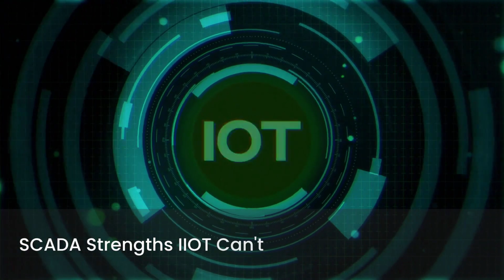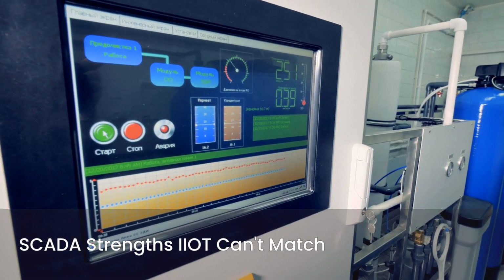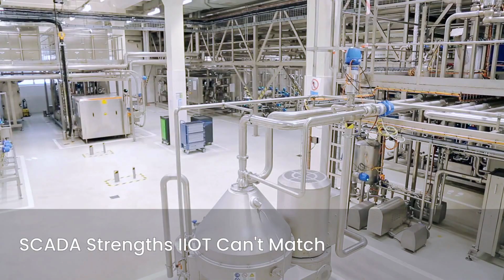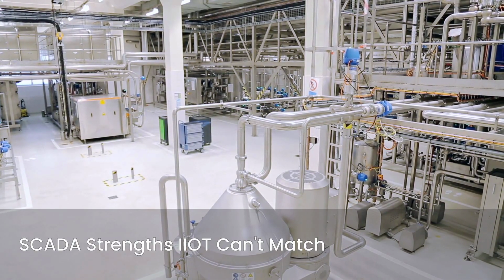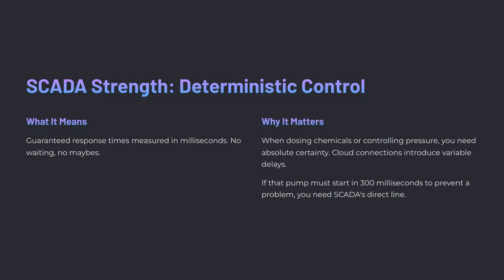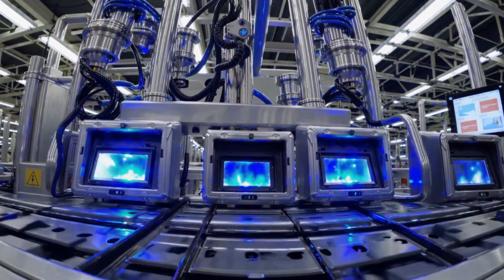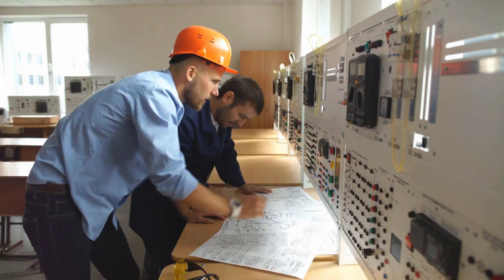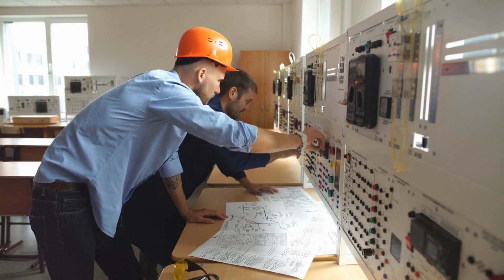So why isn't IIoT simply taking over? Because for the core job of controlling the process, SCADA has strengths that IIoT in its current form often can't match. First, deterministic control. When you're dosing chemicals in drinking water, controlling pressure in a pipeline, or managing a critical safety interlock, you need guaranteed response times, often in milliseconds. Sending a command up to the cloud and back just isn't an option for that critical loop. If that pump must start in 300 milliseconds to prevent a problem, you need SCADA's direct line. I've seen delays cause major headaches, and you just can't risk that on critical loops.